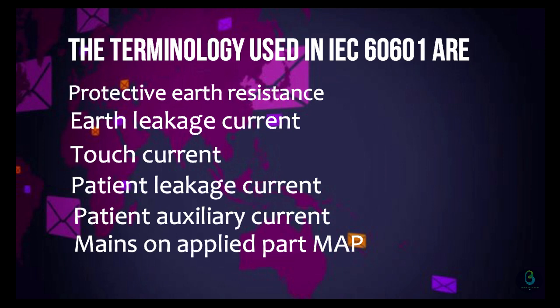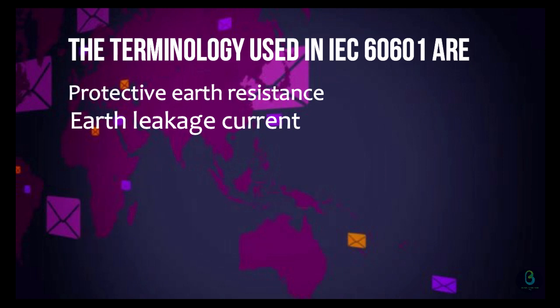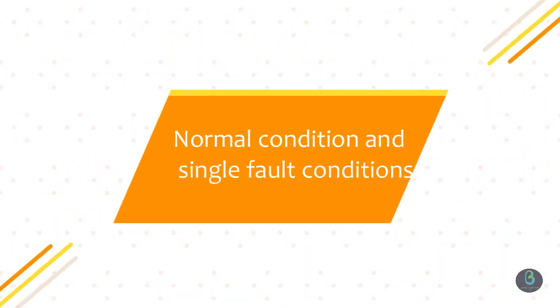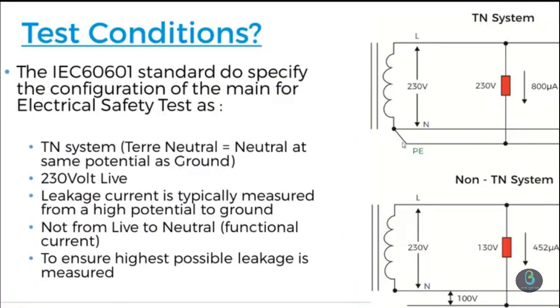Let's understand about some electrical safety terminology. Let's begin with Normal Condition and Single Fault Conditions. A basic principle behind the philosophy of electrical safety is that in the event of a single abnormal external condition arising or the failure of a single means of protection against a hazard, no safety hazard should arise. Such conditions are called Single Fault Conditions.